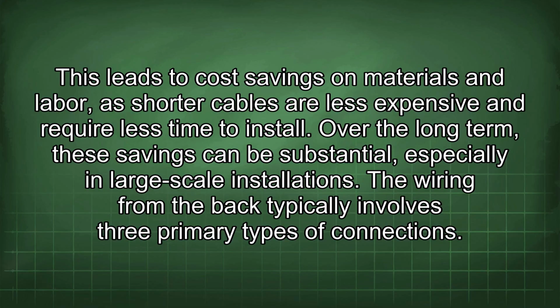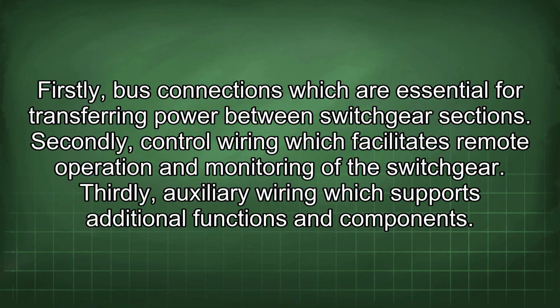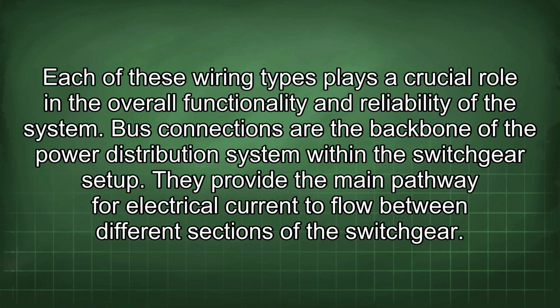The wiring from the back typically involves three primary types of connections. Firstly, bus connections, which are essential for transferring power between switchgear sections. Secondly, control wiring, which facilitates remote operation and monitoring of the switchgear. Thirdly, auxiliary wiring, which supports additional functions and components. Each of these wiring types plays a crucial role in the overall functionality and reliability of the system.